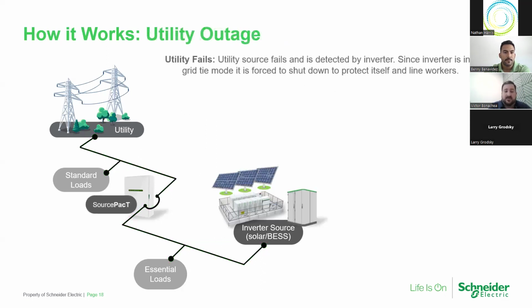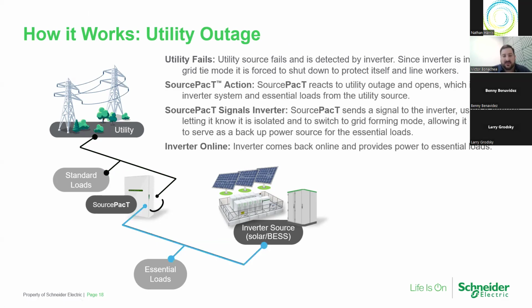Now, when utility power fails, SourcePack or an isolation device is going to detect that because it has onboard metering that is monitoring the utility at all times. When it detects that power failure, it's going to go ahead and isolate the onboard breaker in the SourcePacT, the isolation device. That then islands your essential loads on that emergency sub panel and your inverter together, islands it away from your utility and your non-critical loads.